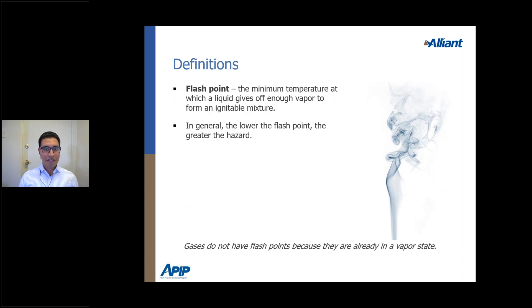Flashpoint is the temperature where the liquid gives off enough vapor to form an ignitable mixture. With flammable and combustible liquids, it's not the actual liquid that ignites — it's the vapor. Once that liquid reaches its flashpoint and starts releasing vapor, that's the point where the vapor could possibly combust.